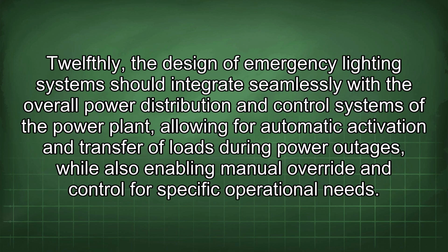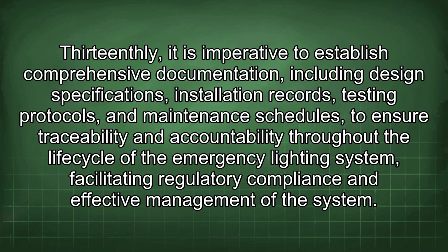12thly, the design of emergency lighting systems should integrate seamlessly with the overall power distribution and control systems of the power plant, allowing for automatic activation and transfer of loads during power outages, while also enabling manual override and control for specific operational needs. 13thly, it is imperative to establish comprehensive documentation, including design specifications, installation records, testing protocols, and maintenance schedules to ensure traceability and accountability throughout the life cycle of the emergency lighting system, facilitating regulatory compliance and effective management of the system.